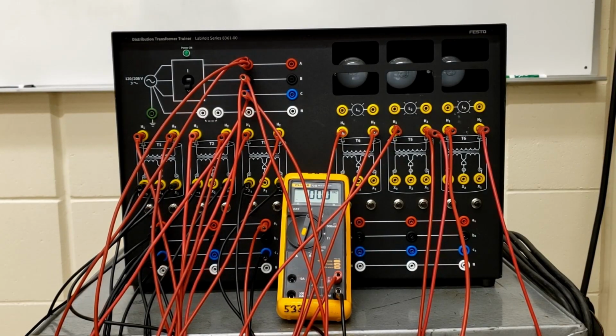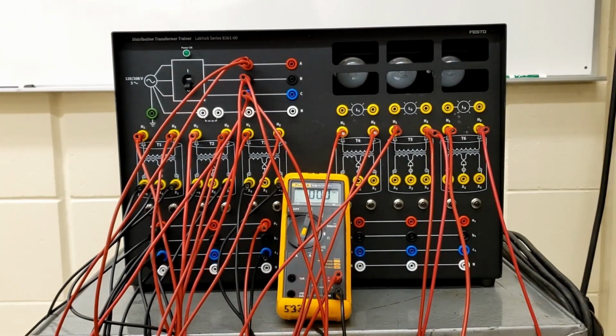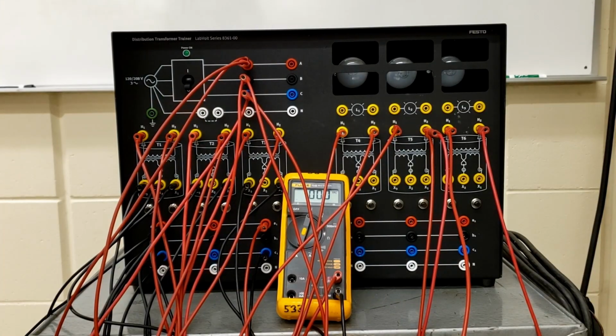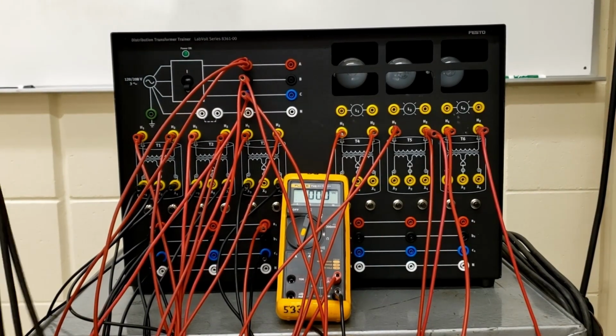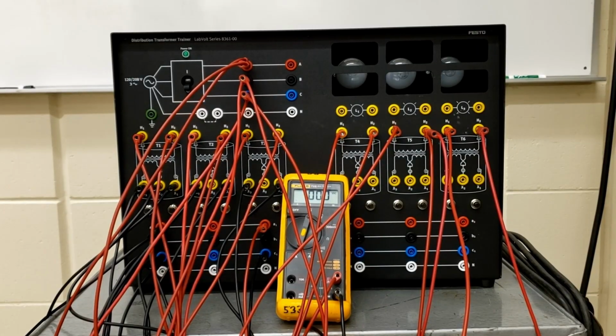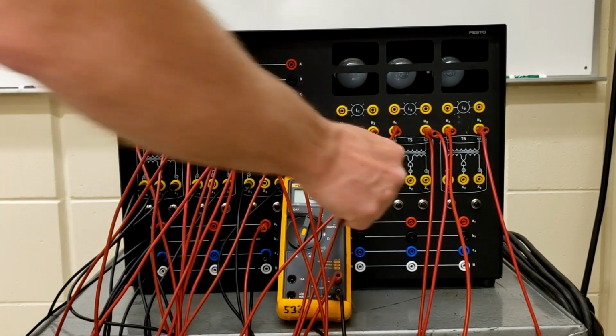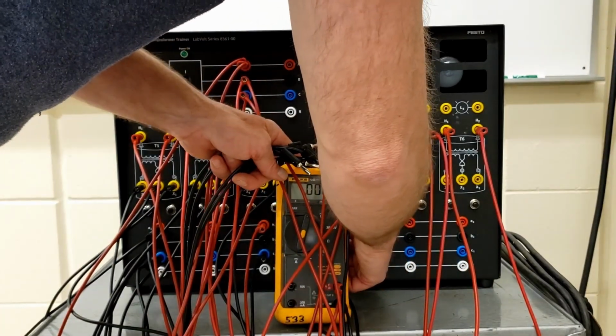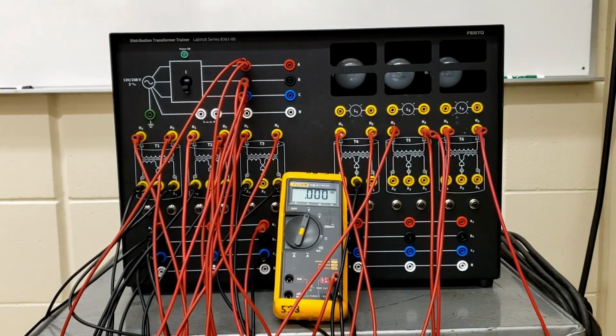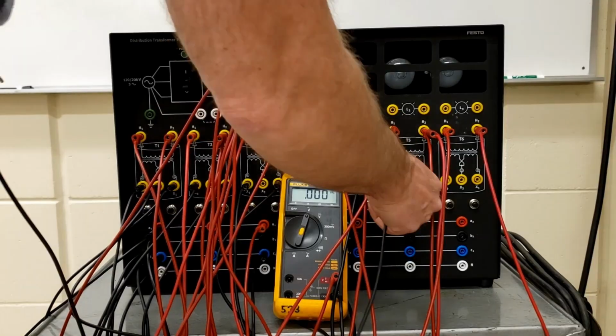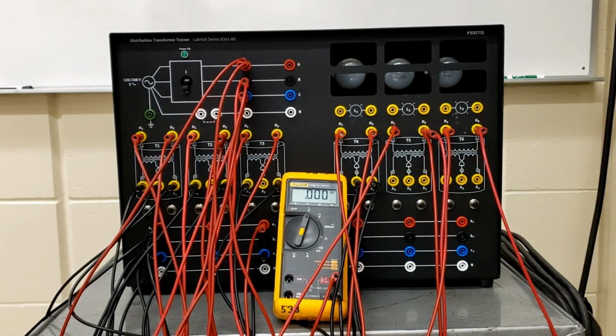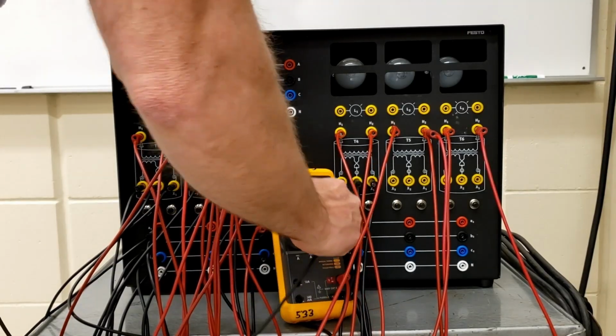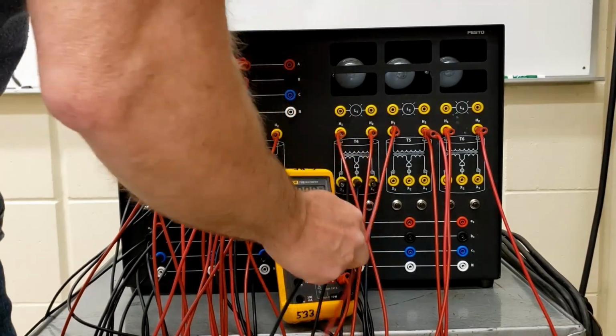Okay, then we need to do the delta on the secondary side there. But these guys are going to be at 210 degrees phase shift now. So let's remind ourselves to do X2 to ground. We have to have a common reference point between the two transformers. Okay, so that's X2 to ground there. Okay, and now we're going to have X1 feeding the B phase. So X1 of our first transformer is now feeding the B phase. X3 is feeding the A phase. So X3 feeding A.